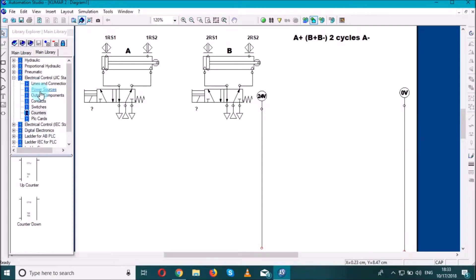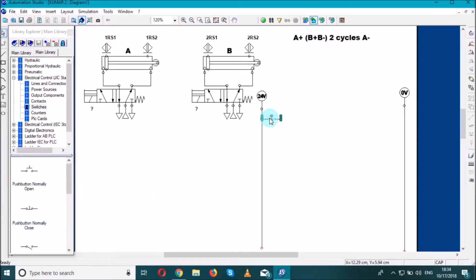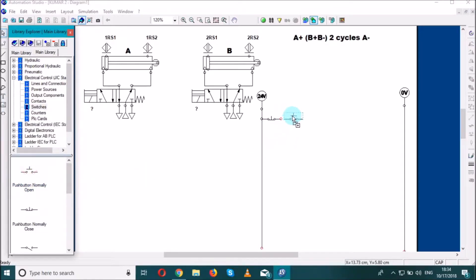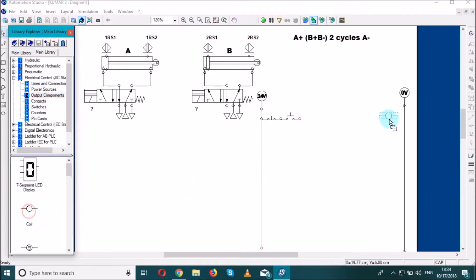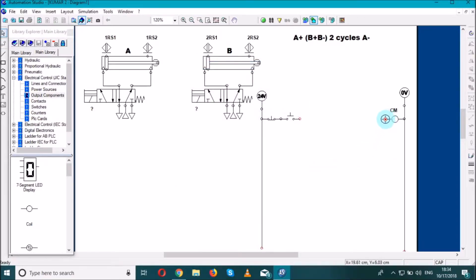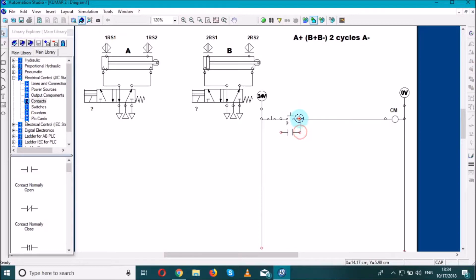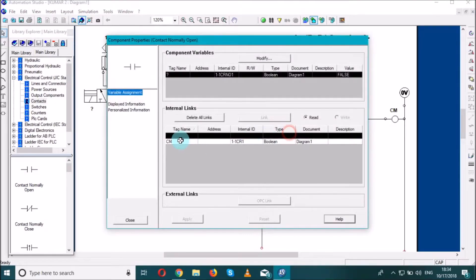In our circuit we will need a 24V power source — we already have it. We need stop and start switches, so we go to switch and search for stop and then start. We also need an output coil, which we'll call CM for main coil. We link it and add a normally open hold-on contact linked to CM.